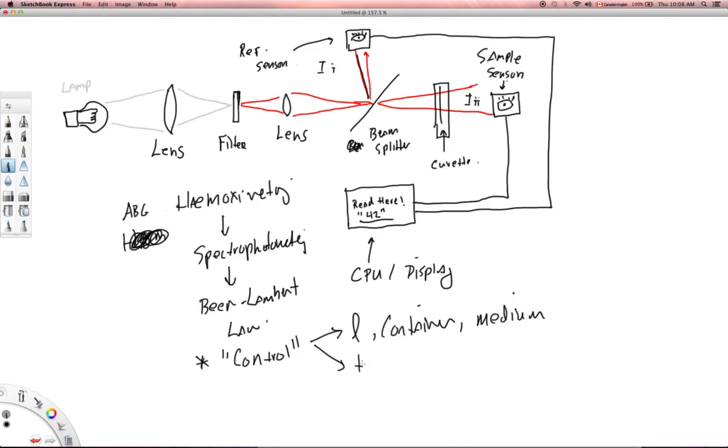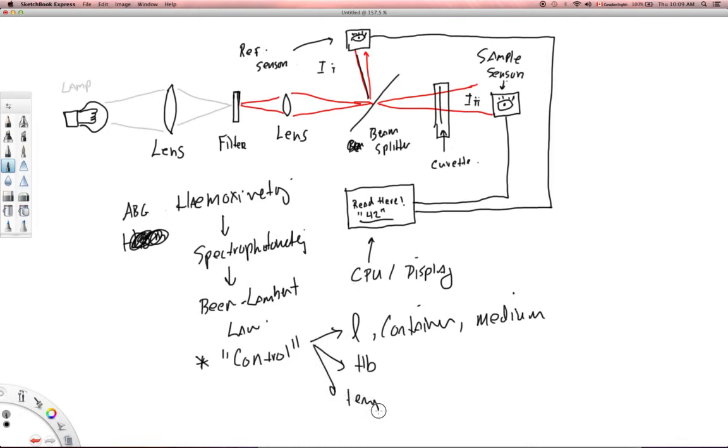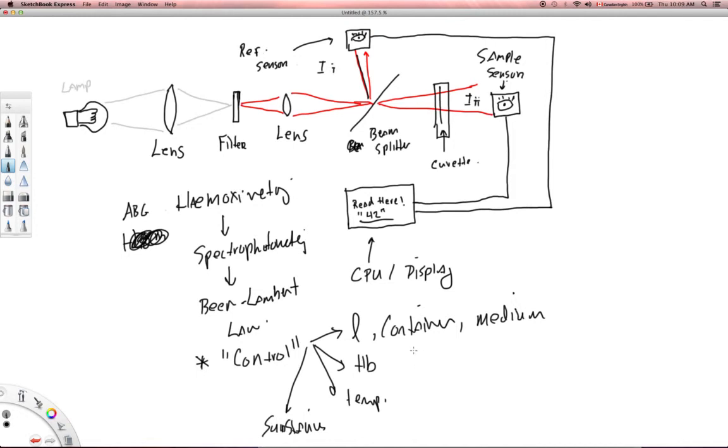And then there's some other things that come into there. Hemoglobin, do I have some weird form of hemoglobin, and has that been accounted for? A lot of these machines are able to look at different types of hemoglobin, methemoglobin, carboxyhemoglobin, et cetera. But that's something you need to ask about. What about the temperature of the sample of blood? And then are there any kind of weird substances or maybe contaminants in the blood that can absorb the same wavelengths as oxyhemoglobin? That can kind of be a confounder. So I just wanted to stress that for this to all work, we have to control for a lot of different things.